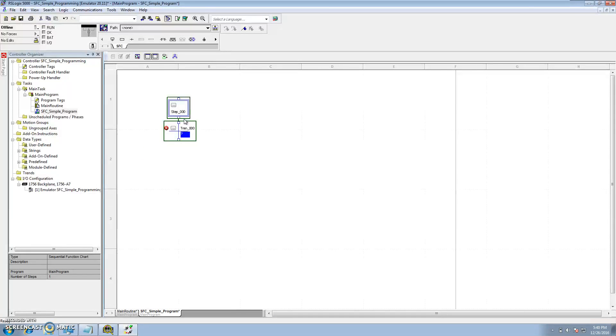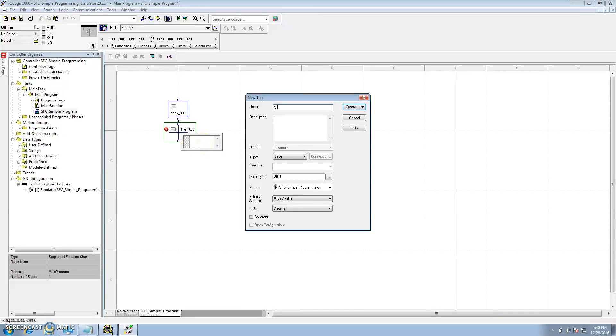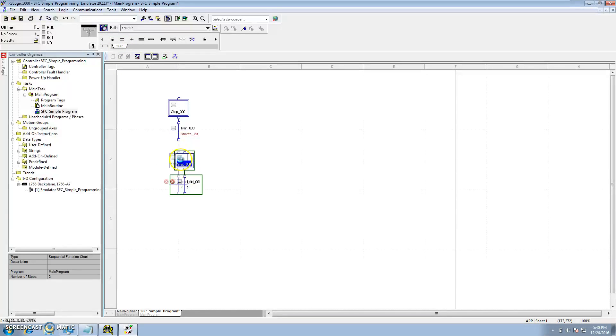We're going to make our own tags. So we'll make a brand new tag: start_PB, which is a BOOL — a single bit. That means it's going to stay in step 0 until the start button is pressed, then it's going to go to the next step. We'll link this transition to this next step.